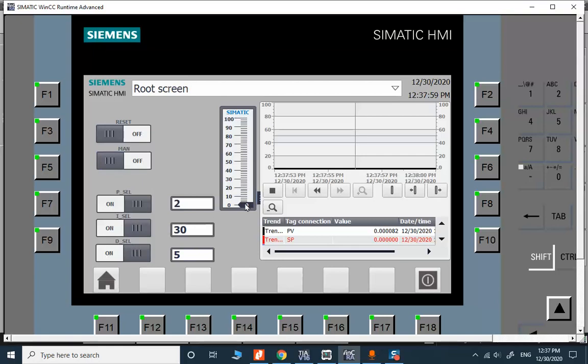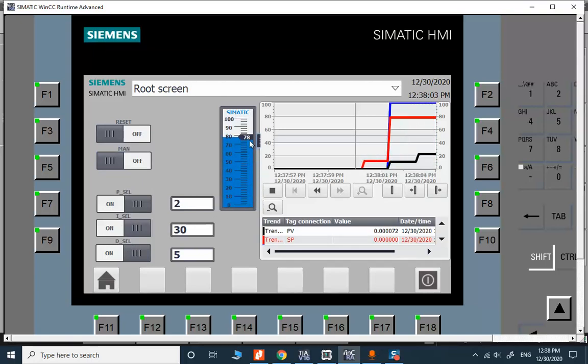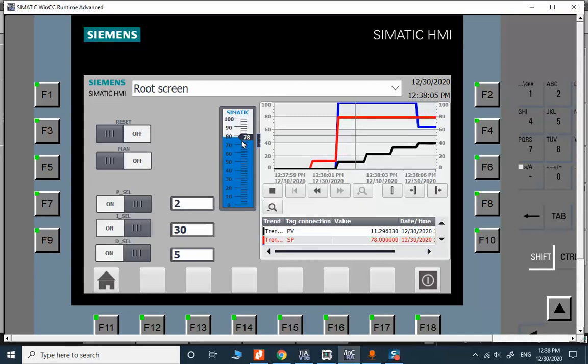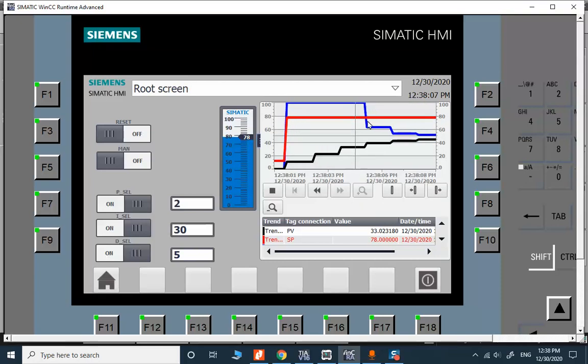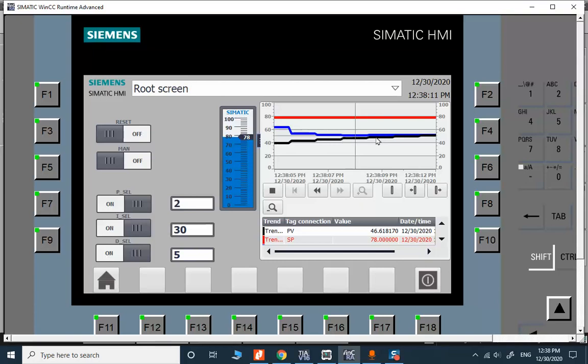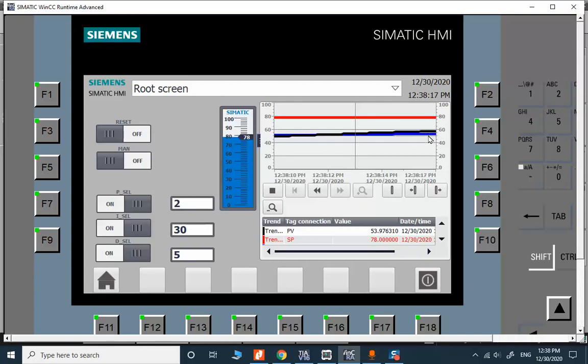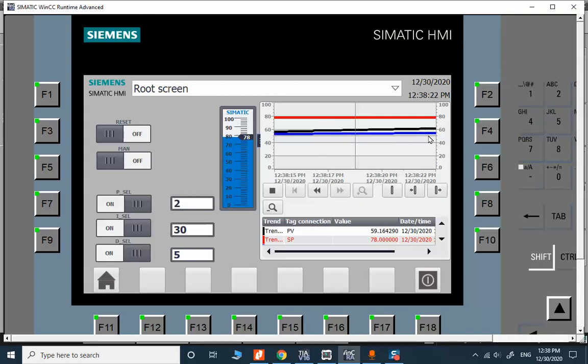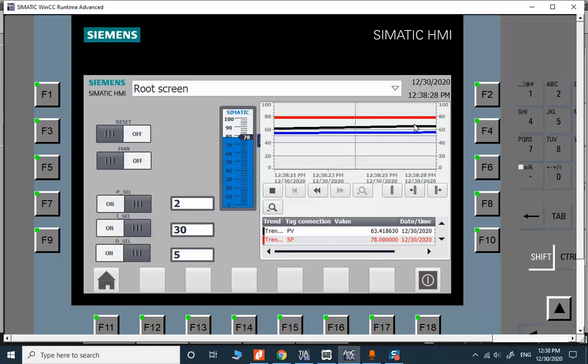For now let me function test the PID controller in PI mode. Let me change the setpoint to 78. The setpoint is the red line and the process value is the black line. We are reaching the setpoint and the blue line is the action on control valve.